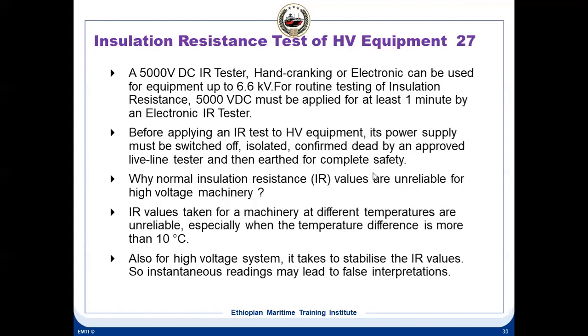When you measure a normal motor, say a generator winding, the first part is that you have to switch off the equipment, isolate it and ground it. Grounding has to be done first, because once it is grounded you cannot apply the megger; of course, you would get all the phase-to-earth values as 0, insulation 0. So first switch off, isolate, ground, then connect your insulation tester, remove the ground, then check.